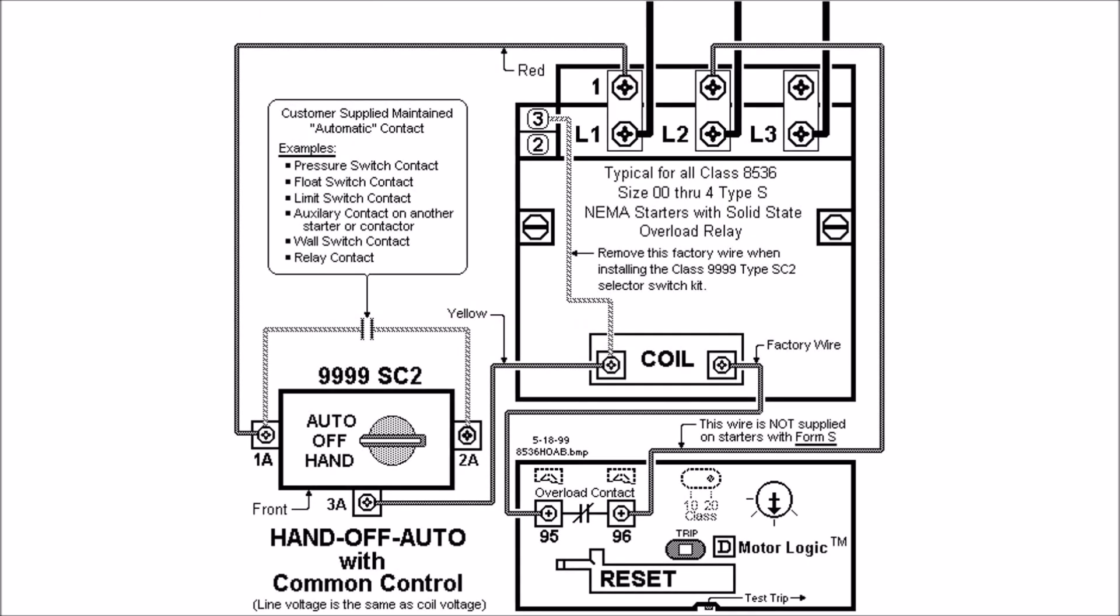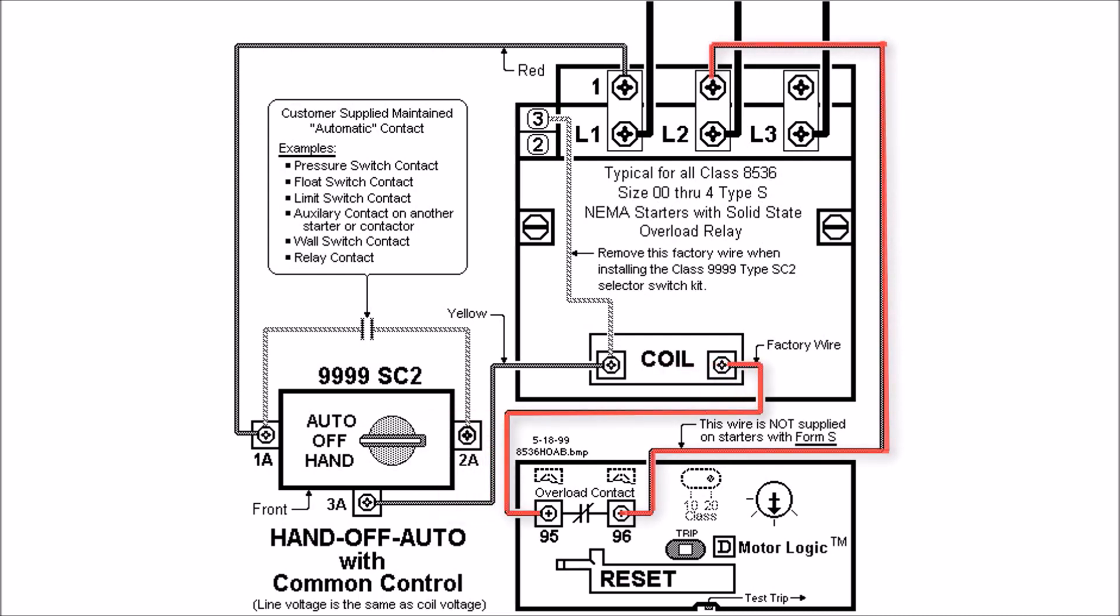For common control, you'll see the wires are a little bit different. You will actually get a starter that does not have Form S on it. This wire from L2, this control takeoff screw behind L2, down to your overload relay will be installed, as well as your 95 to the right-hand side of your coil, as well as that same jumper we mentioned earlier.